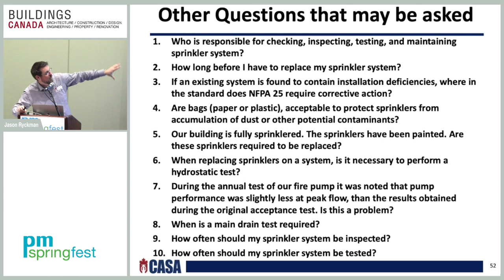Because of time, I'm kind of limited, but I also include some other questions that may be asked. So who's responsible for checking, inspecting, testing, and maintaining a sprinkler system? The owner, right? The owner, or the owner's representative, is fully responsible to make sure that the system is running and operational. How long before I have to replace the sprinkler system? I get questions all the time. How long does a sprinkler system last? The sprinkler system can last as long as you maintain, inspect, and test the system. There's no expiry date on sprinkler systems. It can last forever. As long as you inspect, test, and maintain it, it will last for a long time.